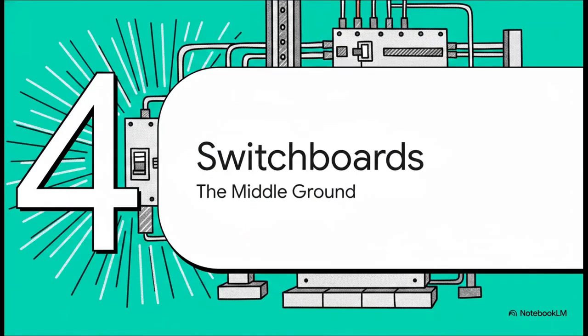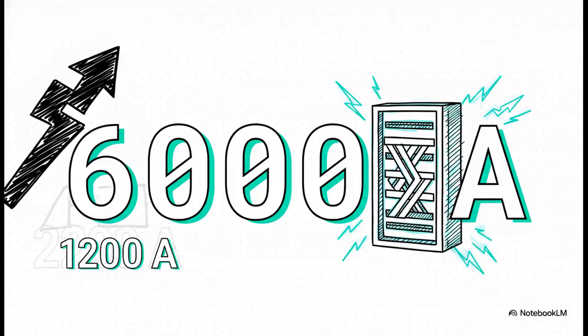Section 4. Switchboards, the middle ground. Let's step it up and look at the real workhorse of commercial buildings. Just look at that massive leap in capacity. We went from a 1200 amp ceiling straight up to a staggering 6,000 amps. That's 5 times the power. At this level, a single switchboard can act as the primary heartbeat for an entire large-scale facility. It takes the massive power feed right from the utility transformer and safely splits it up for the entire building.